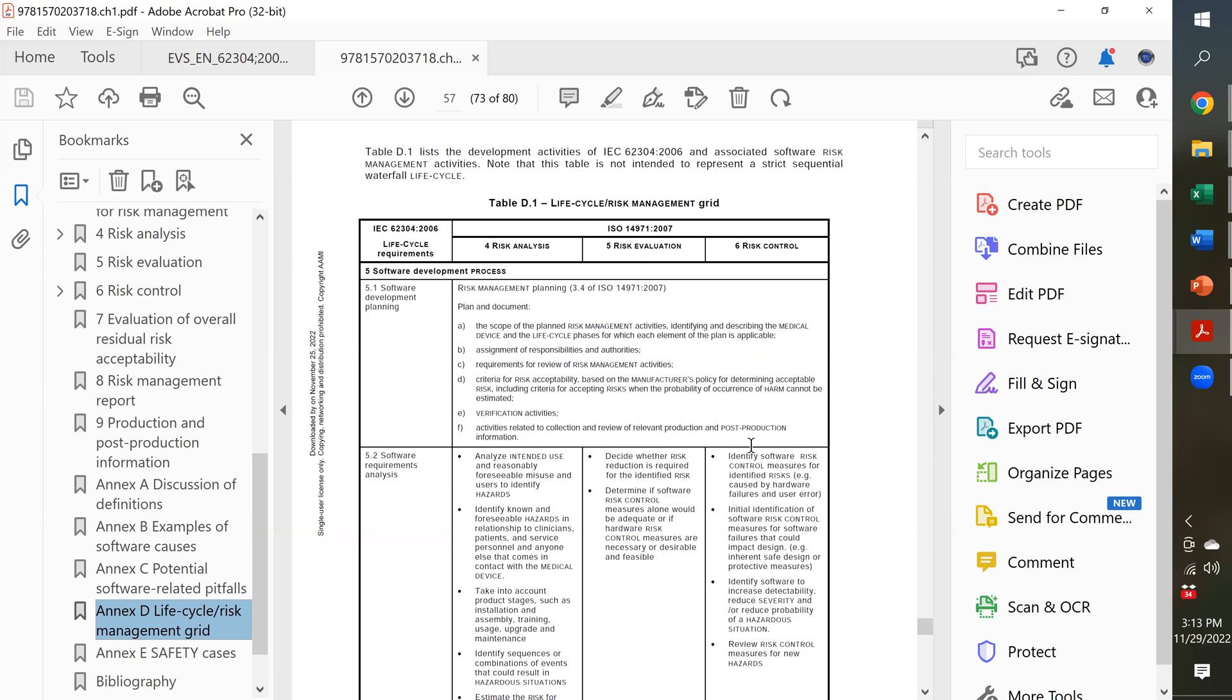Well, for whenever you have a potential hazard, you identified the FDA and the notified bodies, you're going to expect that you've identified a risk control, you've done verification testing, and they're going to want to know where the report is. That traceability is required.